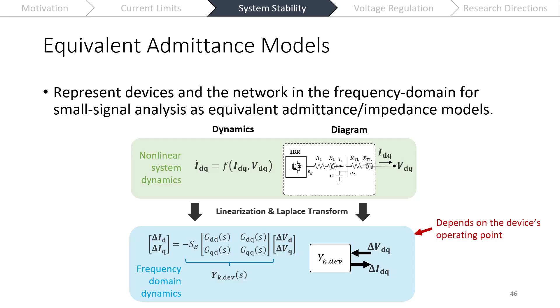One way to try to look at the eigenvalues or the small signal stability for our systems is essentially just linearizing all the nonlinear devices we have in our system and defining something called the equivalent admittance model. So here we have some nonlinear dynamics for our inverter device. If we linearize this and then take the Laplace transform, we get this transfer function matrix that represents the equivalent admittance of our device, which is essentially characterizing how, at least for small perturbations around some operating point, our output current will vary in response to some input voltage. But it's important to note, as we'll see later on, this depends on our device's operating point as well and changes because our device is nonlinear.